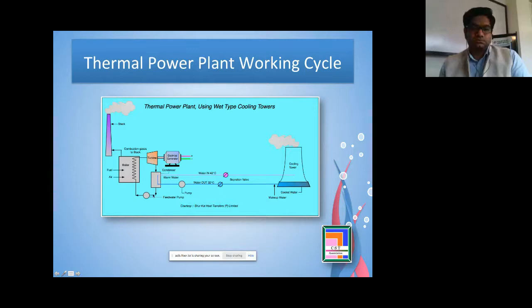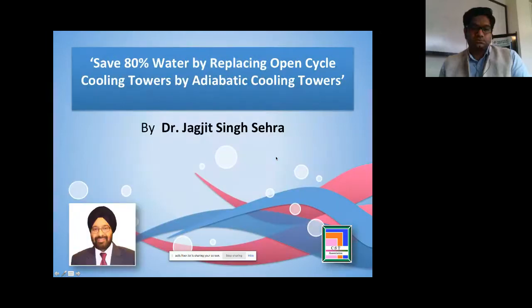So this steam cannot be taken back to the boiler unless it gets condensed. For that, normally shell and tube heat exchangers are used in the power plant, where the steam enters on the shell side, and on the tube side there's a pump which circulates the water inside the shell and tube heat exchanger, which goes to the cooling tower, sprays the water there, and the cold water comes at 32 degrees centigrade. So now this is the point where we get a lot of evaporation of the water.